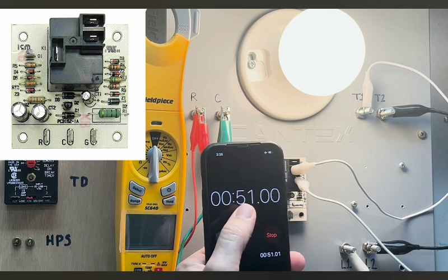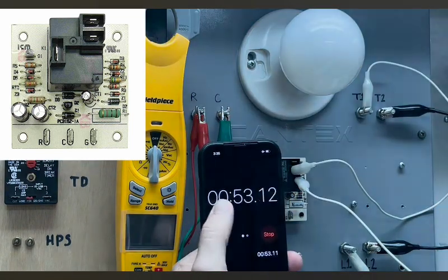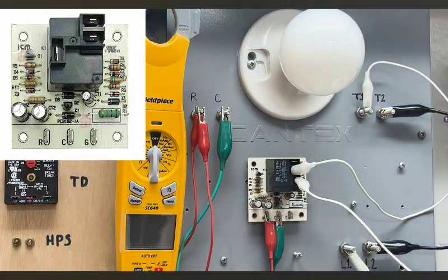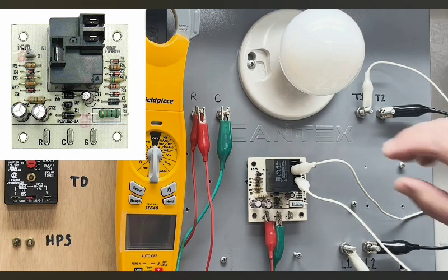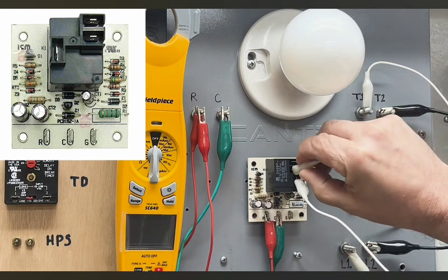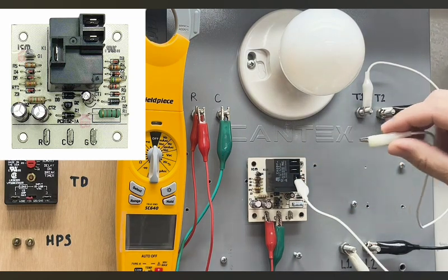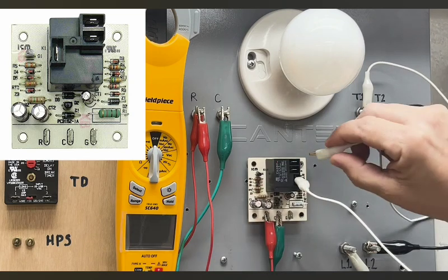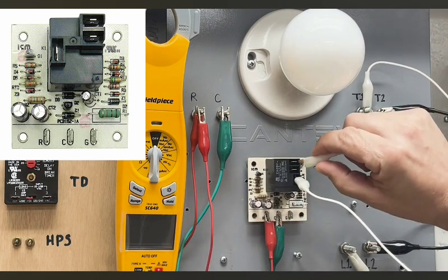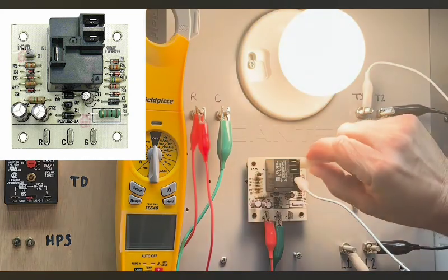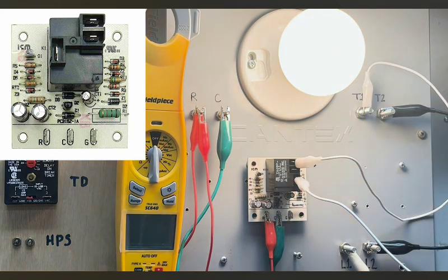All right, so now we have 50 seconds. We're at 52. There we go. And so a little bit of consistency there, not bad. Now we're going to go ahead and take our normally open terminal and pull the wire off of that. We're going to put the wire on the normally closed terminal. As you can see here, the load is energized. I'm going to do the same thing.